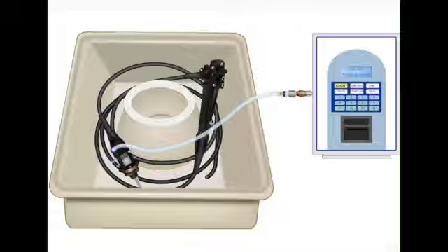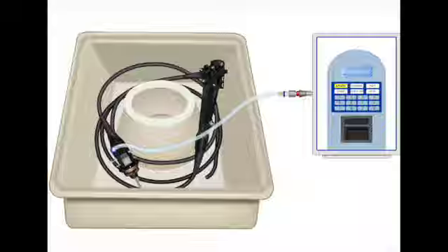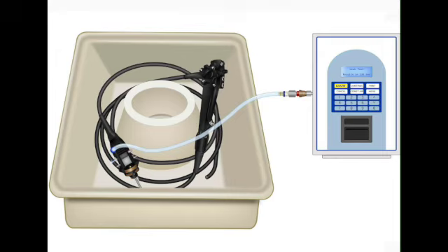And error number 3 goes back to something you said was critical right at the beginning. Failing to angulate, not moving the tip. Not turning the knobs. If you don't flex that bending section, you're not testing the O-rings under strain. It might pass a static test, but it's still a compromised scope, just waiting to flood during the next cleaning cycle. Which brings us back to the ultimate impact of any of these errors.